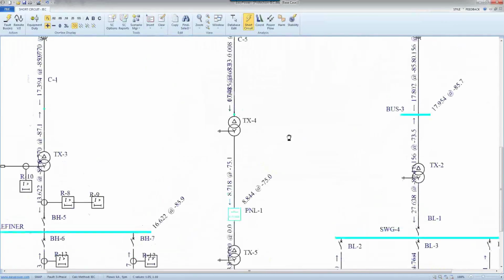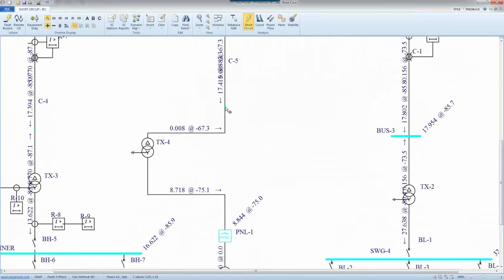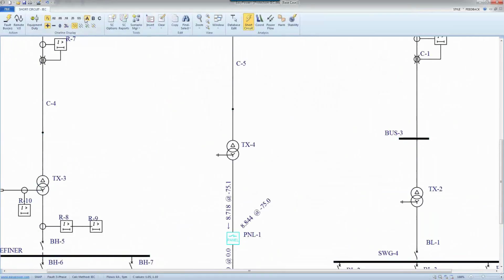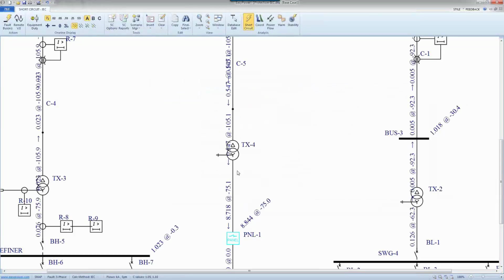The phase shift again was 30 degrees. So I increase this one. Okay, minus 71. In fact, let me fault somewhere that would make our calculation a little bit easier. Maybe I can fault here. That would probably make it a little bit easier for us. Okay, and I removed values. So that makes it easier because both arrows are in the same direction. Minus 75, 30 degrees, minus 105.